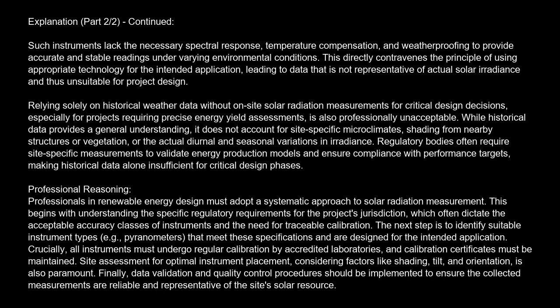Relying solely on historical weather data without on-site solar radiation measurements for critical design decisions, especially for projects requiring precise energy yield assessments, is also professionally unacceptable. While historical data provides a general understanding, it does not account for site-specific microclimates, shading from nearby structures or vegetation, or the actual diurnal and seasonal variations in irradiance. Regulatory bodies often require site-specific measurements to validate energy production models and ensure compliance with performance targets, making historical data alone insufficient for critical design phases.